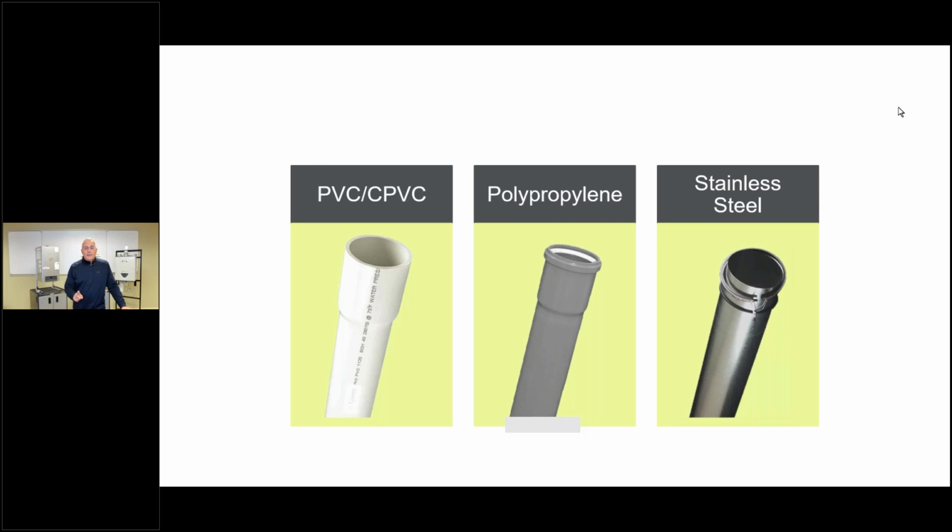All right. Oh, but the manufacturer gave you a piece of CPVC to put on top of the appliance before you transition to PVC, and that should be my get out of jail free card. The reason they do that is because that would be the hottest spot right at the top of the appliance, but still your venting material is incorrect at that temperature. So you really have to be aware: if I'm going to put in that appliance and I can vent it properly, okay, great. What temperature am I running that system at? Because it has a profound effect on the material that you use.